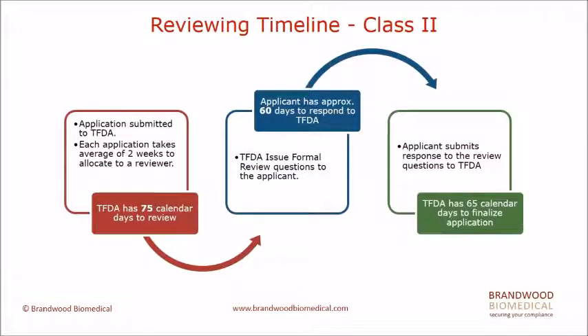Now we're going through the TFDA reviewing timeline and reviewing process for Class 2 devices. Once the submission is submitted to TFDA, the manufacturer or the sponsor can expect to hear back the initial feedback from Taiwan FDA in 75 calendar days, roughly about 2.5 months, with formal review questions. Then the manufacturer and the sponsor have 60 days to respond to TFDA.